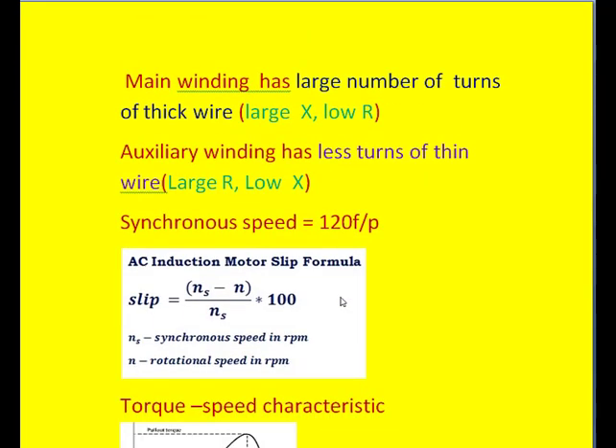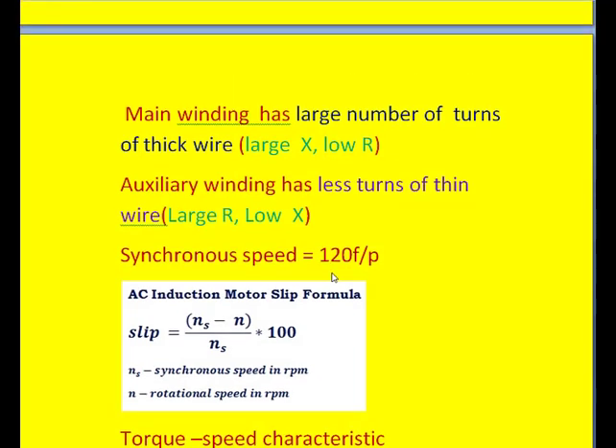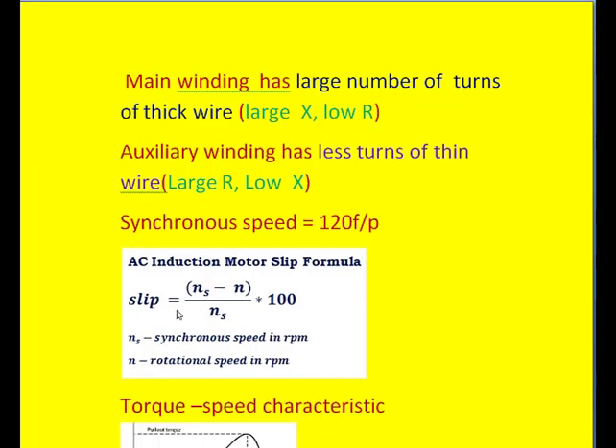Next, we see the definition of synchronous speed. Just like in the three phase induction motor, here also we find the stator magnetic field speed, which is also called synchronous speed, given by 120F divided by P. Here P indicates the number of poles of main winding. If the main winding is wound for four poles, the auxiliary winding is also wound for four poles. Similarly, we find here a definition called slip, which is nothing but synchronous speed minus rotor speed divided by synchronous speed.